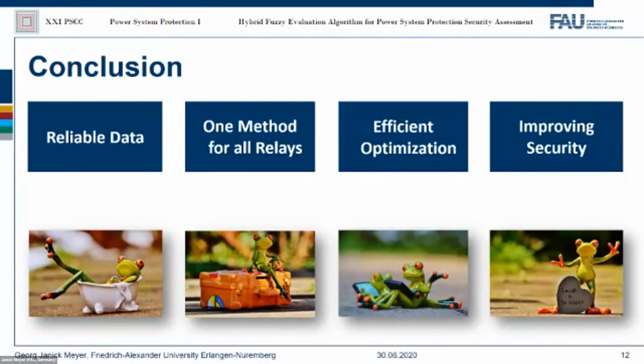So to conclude, the new hybrid evaluation algorithm for protection security assessment uses reliable simulation data as underlying reference data to build up its fuzzy sets. Using the evaluation criteria, dependability and security, all protection relays of a system-wide grid can be assessed with the same evaluation method. Every setting of every relay has its own fuzzy set, but all sets are combined to one protection security index. Using an efficient optimization algorithm, it is possible to find the best compromise in complex grid structures and the best settings for all relays simultaneously. Validated by the proven PSA method, our new approach is able to improve system security.